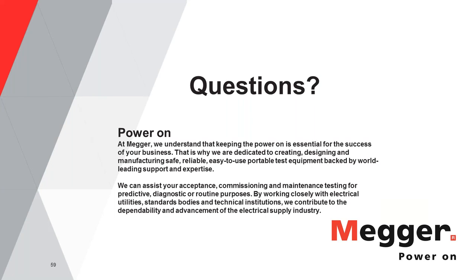To your question, is it recommended or should we perform the test at rated voltage? That kind of test would be destructive, because then you are doing the test at both high voltage and high current. That's the reason why in the factory, at the OEM place, in a full batch, they would randomly pick a few breakers and test at rated voltage and rated current to make sure that the insulation is of right strength, the poles are separate apart, they can handle the current, those kinds of things. As I said, out in the field, you perform the test at high current and low voltage, and those tests are non-destructive tests.